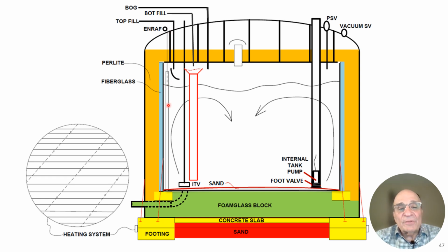And the ENRAFs are typically in what's called a stilling well. A stilling well is nothing more than a tube, let's say a 6-inch or 8-inch diameter tube, that has many holes drilled in it to avoid having waves. Let's say you're top filling and you're getting some agitation. You don't want this ENRAF to be bouncing in here and wearing out your spool. You want it to be relatively steady. So that's why the stilling well is used. And you typically would have 3 ENRAFs on a tank.